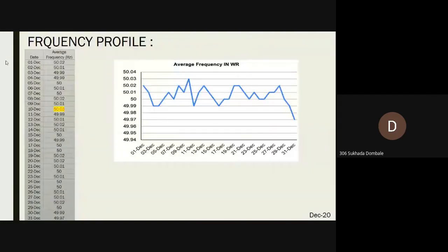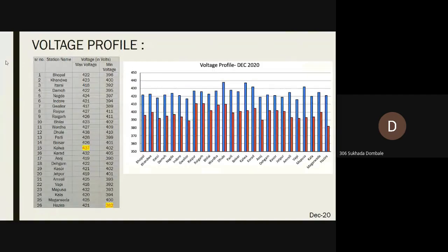Next, we will see the frequency profile. The graph shows day-wise frequency variation on each day. The maximum frequency was 50.03, which was observed on 10 December 20, and the minimum frequency was 49.97, which was observed on 31 December. Next, we will see the voltage profile in western region. The maximum voltage is observed on Kalwa station, which was 437 volt. The minimum voltage is observed on Hazira station, which was 382 volt.